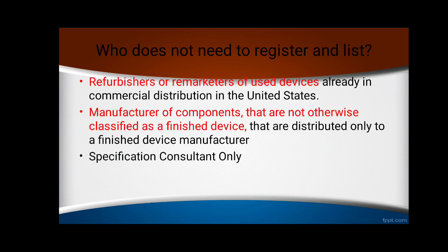Refurbishers or remarketers of used devices already in commercial distribution in the United States are exempt. Manufacturers of components that are not otherwise classified as finished devices and that are distributed only to a finished device manufacturer are exempt. A specification consultant only is also exempt from FDA registration and listing.